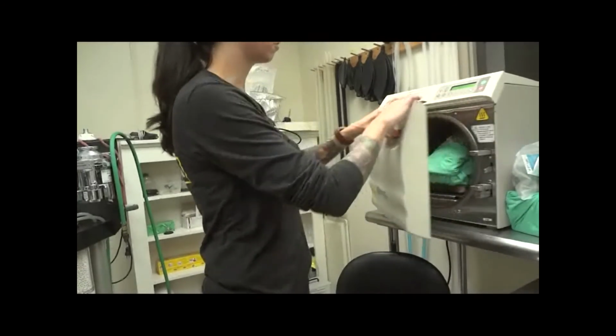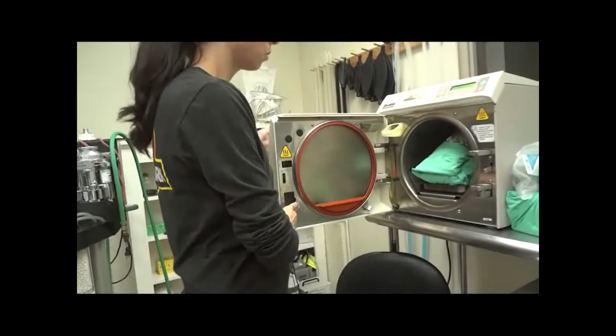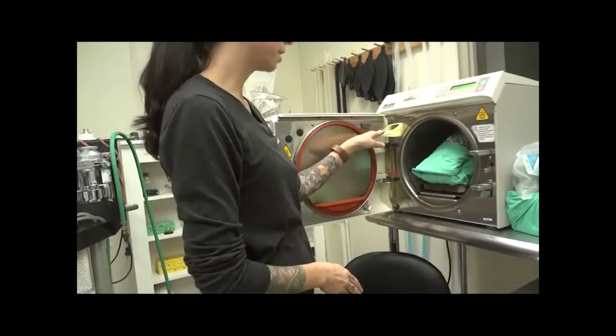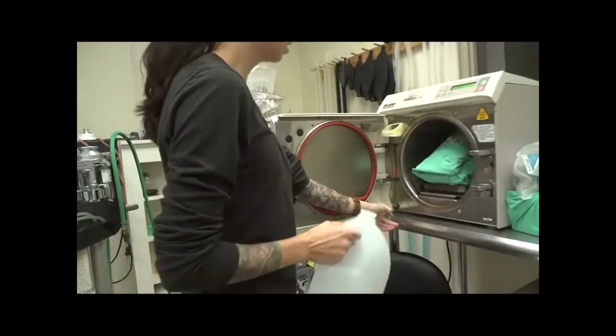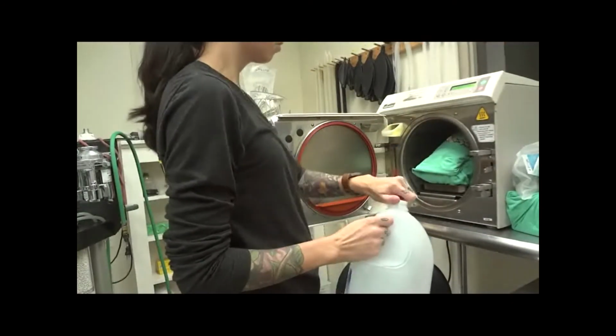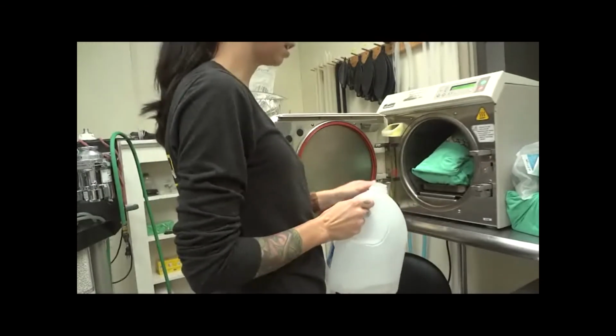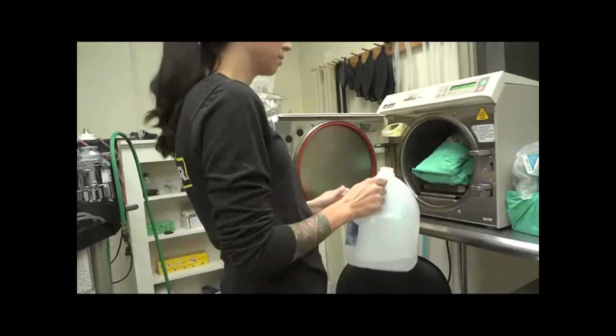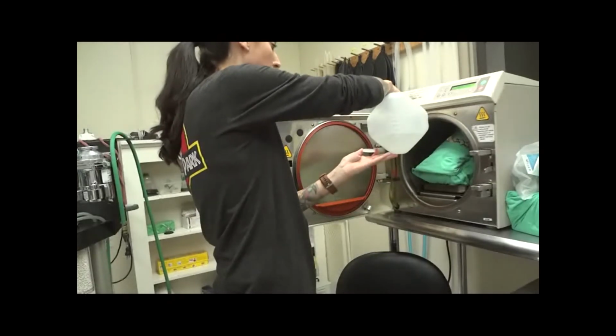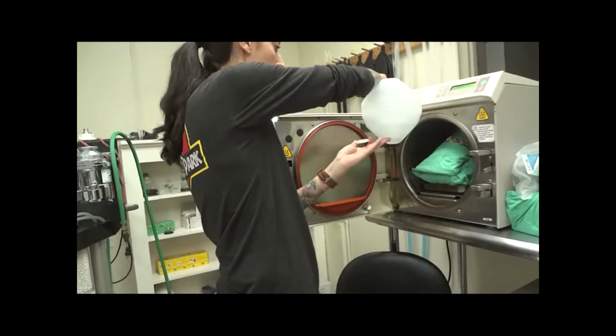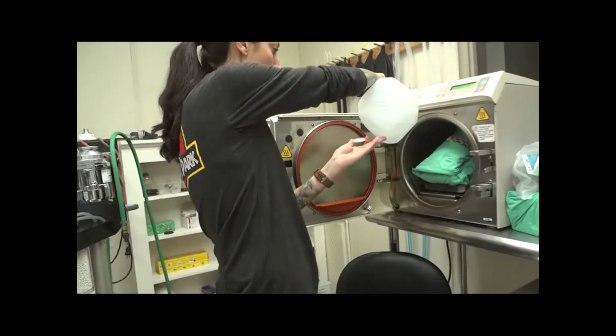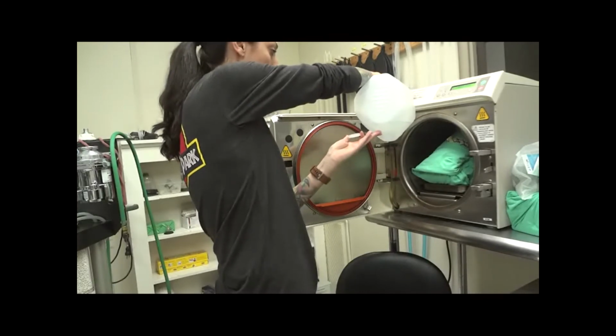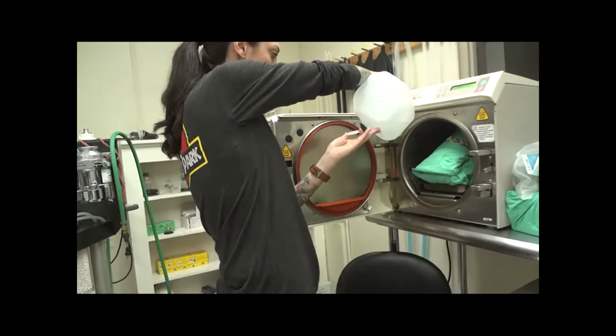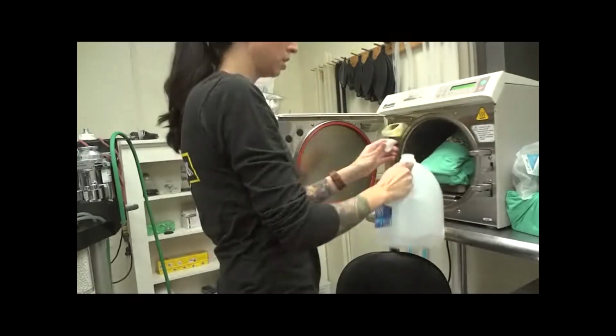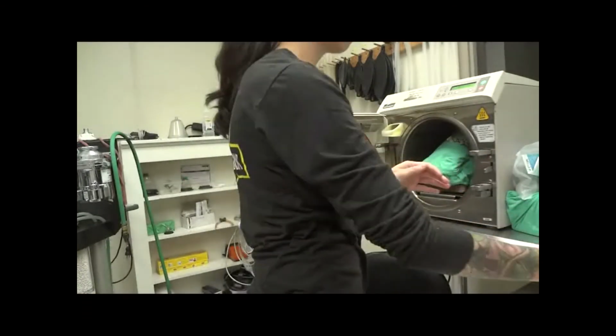To maintain our autoclave, we would fill with distilled water right here in this little cup, and then it fills the tube. When it needs to be properly maintained and cleaned, we do send our autoclaves out to a proper facility. It needs to be filled after each cycle or each run.